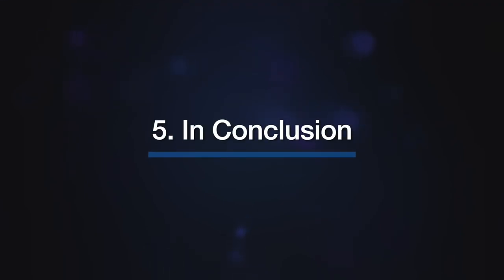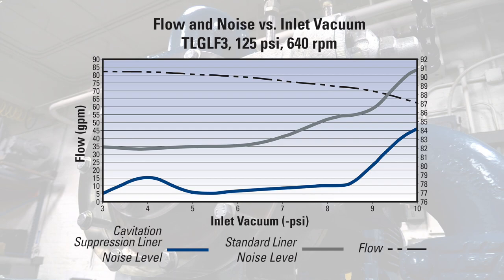To summarize our findings, the unique characteristics of the Blackmer cavitation suppression liner can greatly reduce the damaging effects of cavitation by managing the entrained gas bubbles inside the pump. As seen on this graph, the positive results can lead to a measurable reduction in vibration, noise levels, and ultimately reduced wear and tear on internal pump components. This technology is especially beneficial when NPSH required is greater than NPSH available.